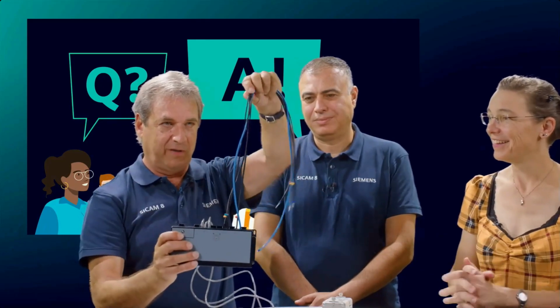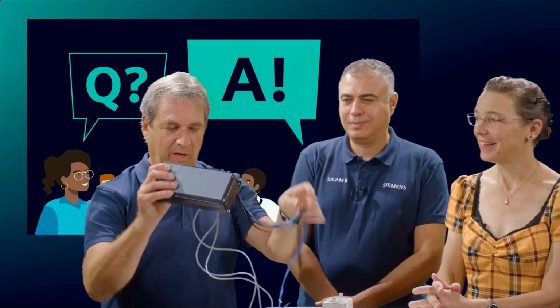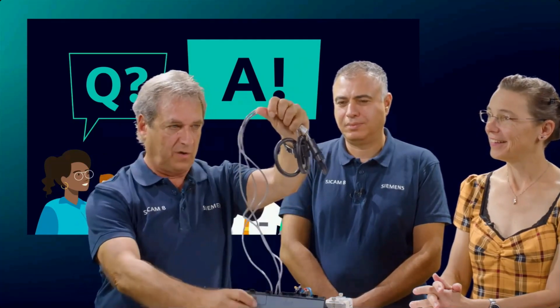But the wired inputs are limited because they are calibrated. This is for 230 volt AC, and this is for, let's say, the connection of real currents starting from several amperes going up to 1,000 ampere. So we are not talking about milliampere. All right, thank you. I hope that answered the question.